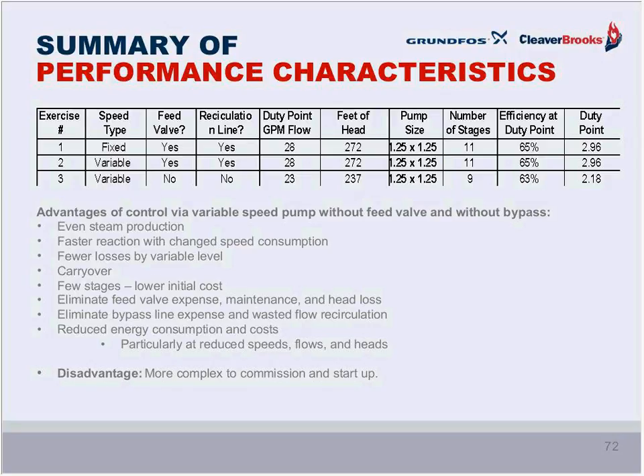And in some applications, that can actually allow you to purchase a smaller motor, which is a further upfront cost reduction. So you can see what the advantages are to the variable speed control method when those feed valves and recirc lines are eliminated. And better steam quality is certainly one of the chief reasons. Service and repair costs on the feed valves go away.